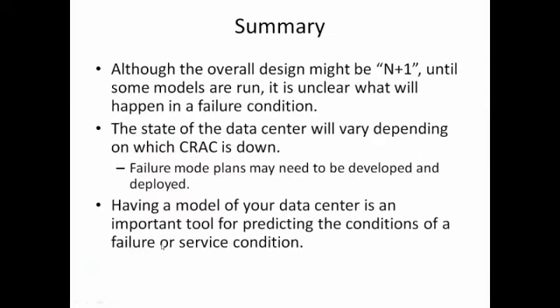All right. So, summary slide on this section, and we're going to take a quick look at another design as well. But I think the point here is that even though the design may be N+1 on paper, unless somebody runs some models on it, it's unclear what's going to be happening in a failure condition. And over time, if you don't have a model of your data center that is representative of what's going on, and your IT loads change and people move things around, it's unclear that it's going to behave itself in a failure mode. So it's going to depend on which one is down. And I would argue that plans need to be developed and put in place prior to having it hit you in the face, if you know what I mean, right, Magnus? Right.